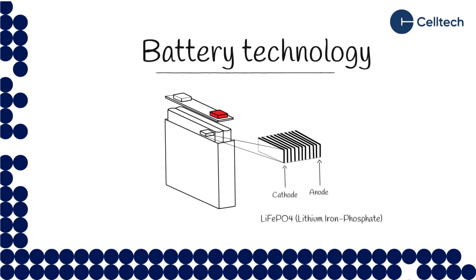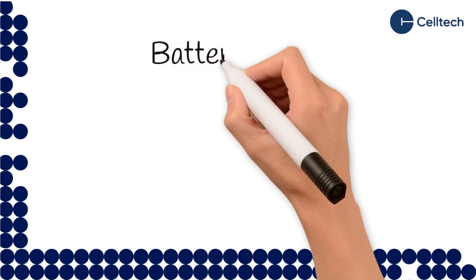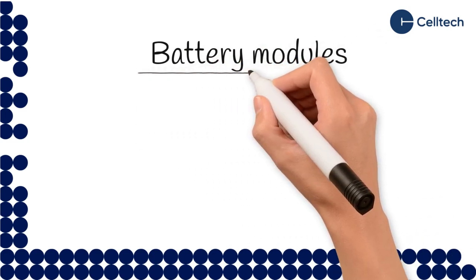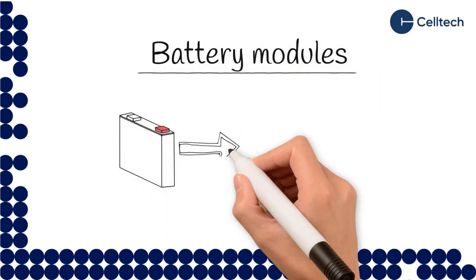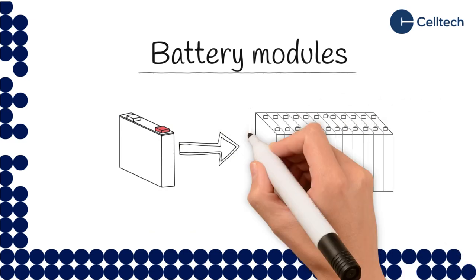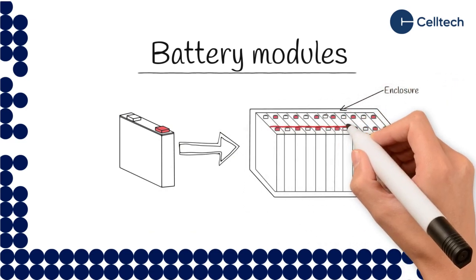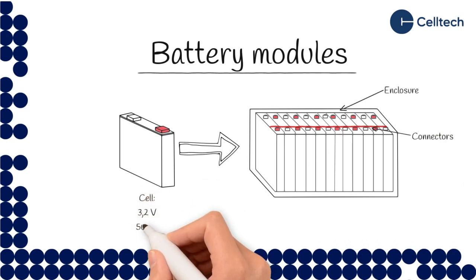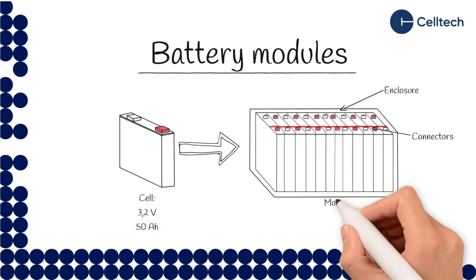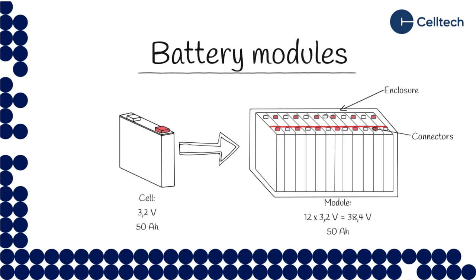For example, in LFP batteries the cathodes are made of lithium iron phosphate (LFP). When you pack several cells together you get a module. The cells are typically in a plastic, metal, or aluminium enclosure, connected with connectors inside the modules. The cells are connected in series or parallel to achieve the desired voltage and energy capacity.